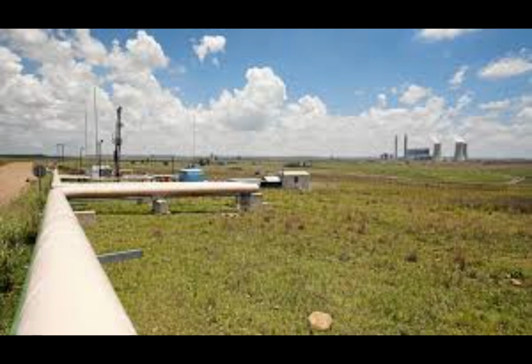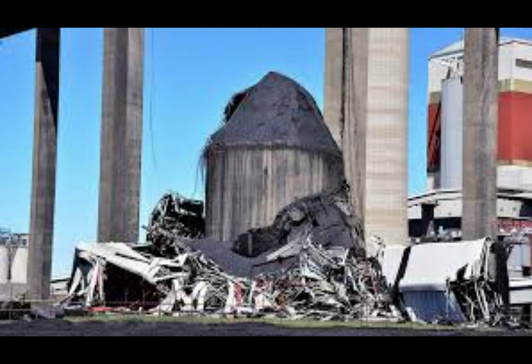Silo collapse. On November 1, 2014, the plant was running under normal load when a visible crack was reported on Silo 20 by a member of the operating staff at approximately 12:30. Personnel in the area were subsequently evacuated. At 13:20, the silo collapsed, and the plant's output was immediately reduced from 3,600 megawatts to 1,800 megawatts.